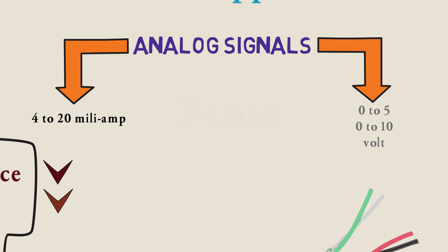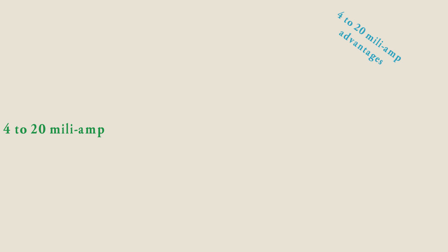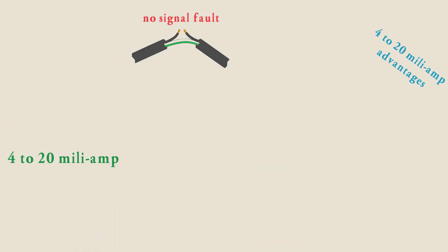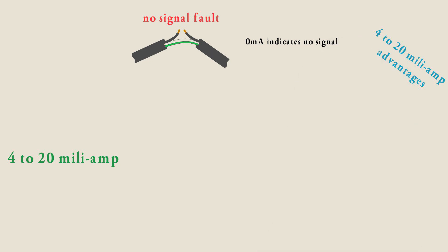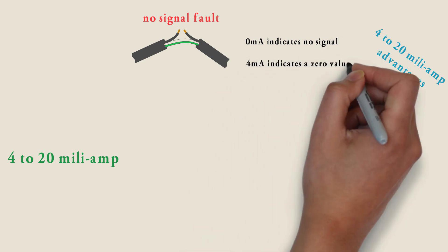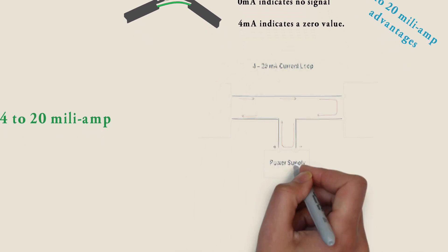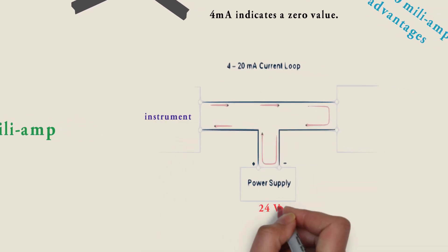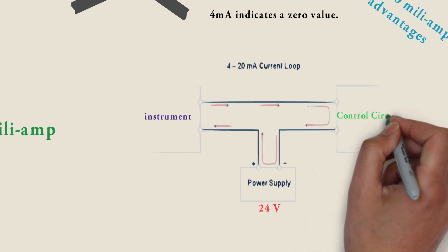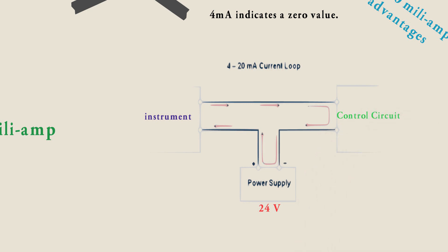The 4 to 20 milli-amp current signal offers some real-world advantages, such as: a no-signal fault can easily be detected. 0 mA indicates no signal, while 4 mA indicates a zero value. An instrument can be loop-powered, often with 24 volts DC, so it can be powered by the same cable that instrument transmits on.